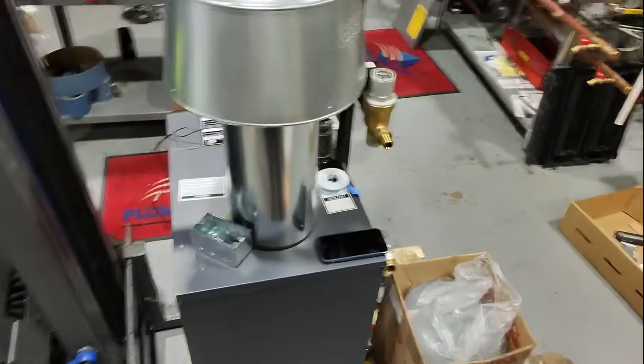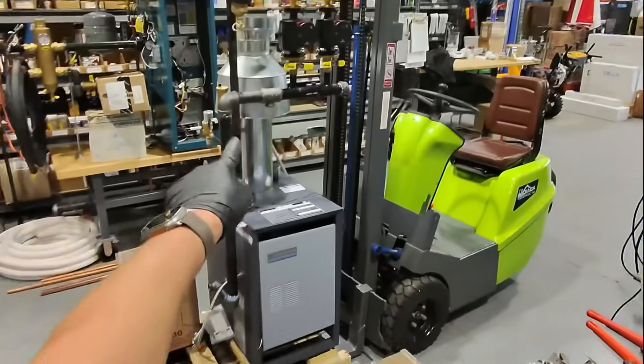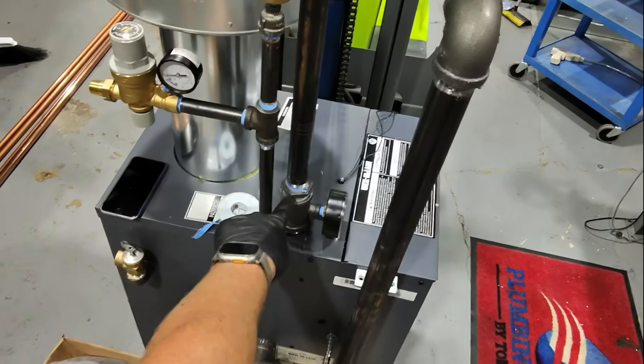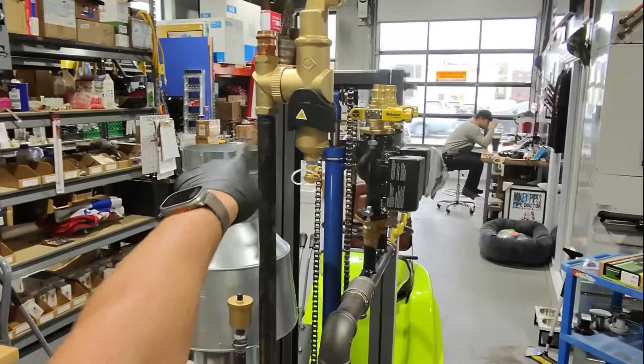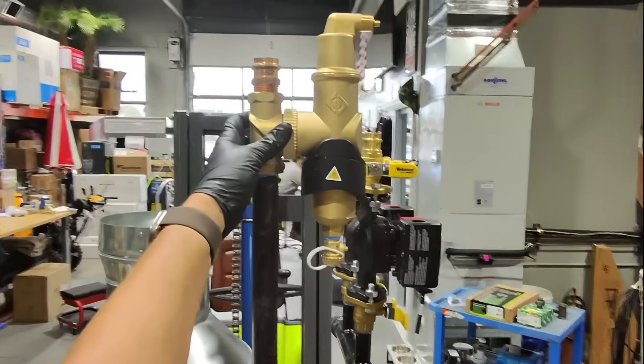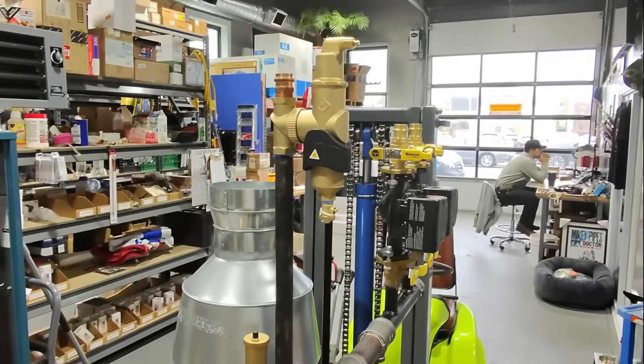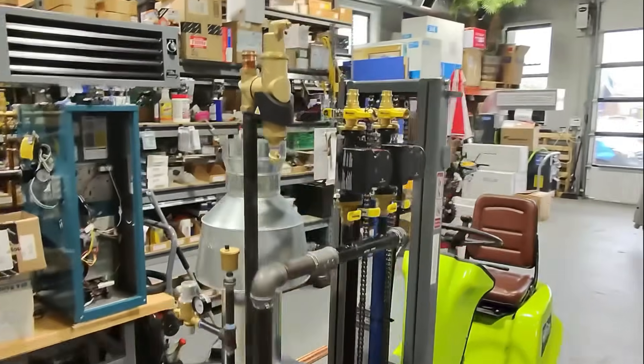We'll put on our check valve and valve on site to connect our domestic water to the boiler. We'll also put on the boiler drain on site - I don't want it to be too wide and become a problem when we bring it into the house and down the stairs. That tridicator gauge is connected to the inch-and-a-quarter by quarter-inch T with that inch-and-a-quarter by one-inch bushing. I threaded a piece of one-inch and I have a one-inch vertical air separator by Spirotherm - the spiral vent, beautiful, magnetic. From here we'll connect to the one-inch that is the boiler system supply.